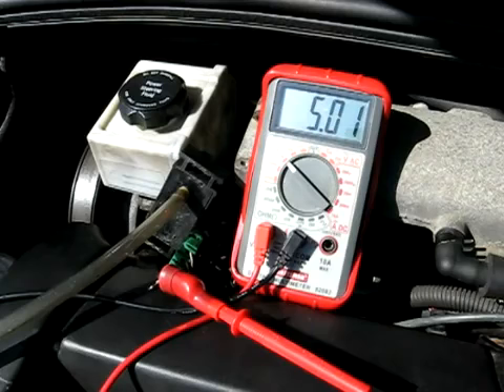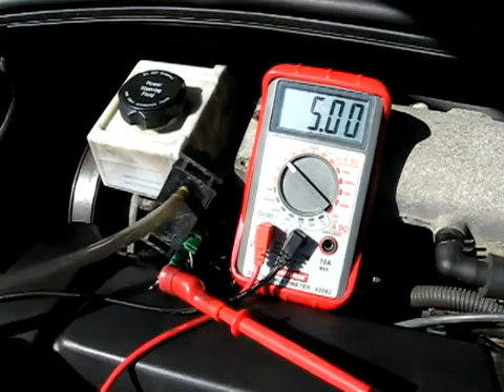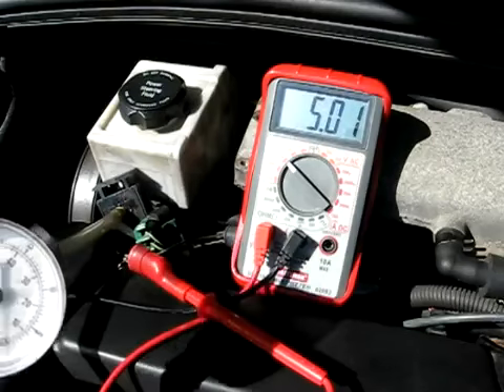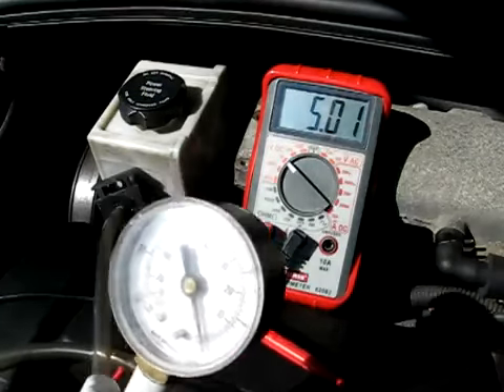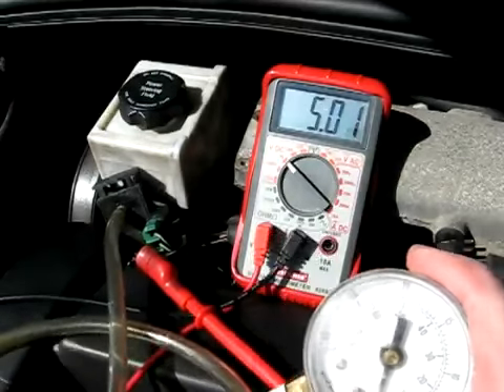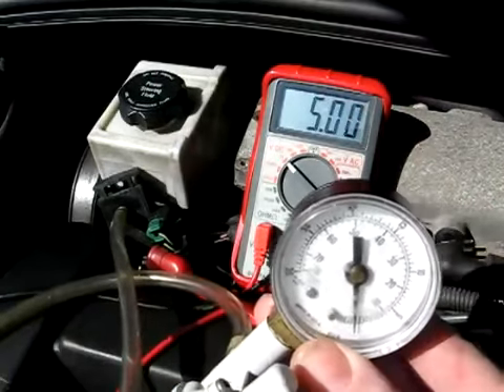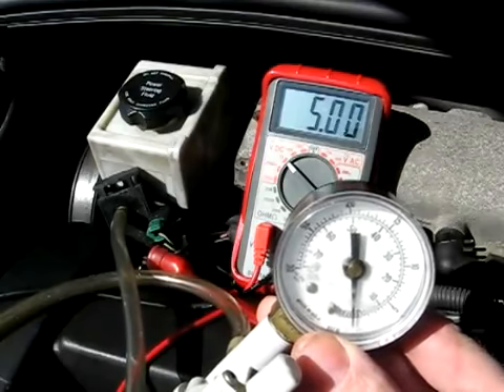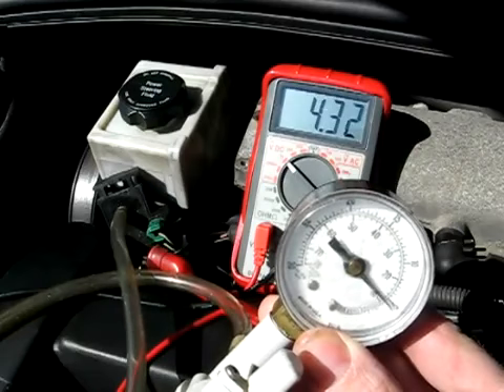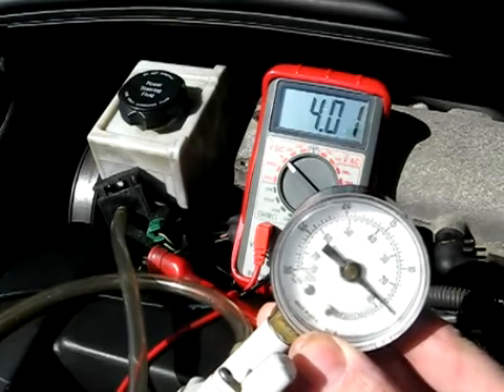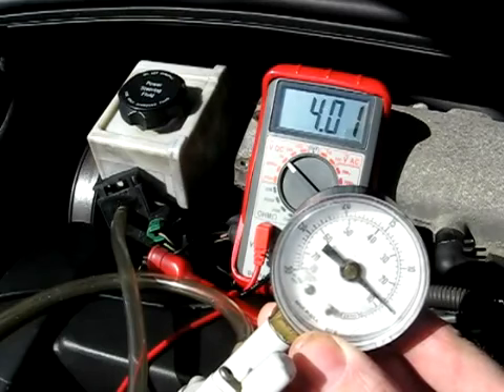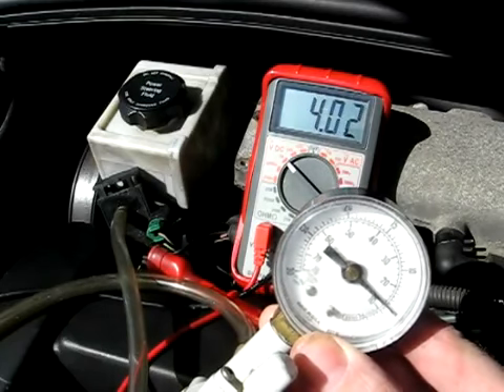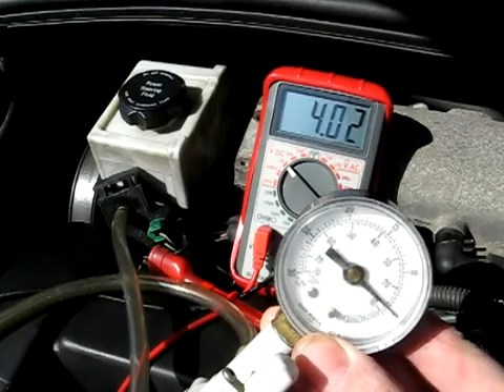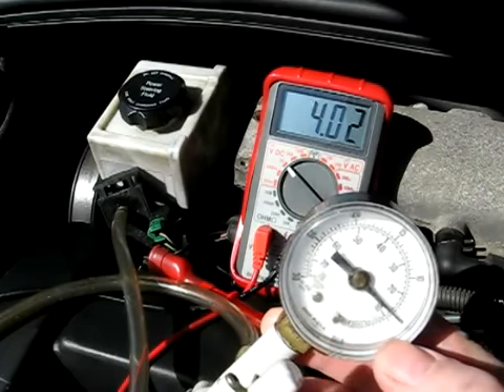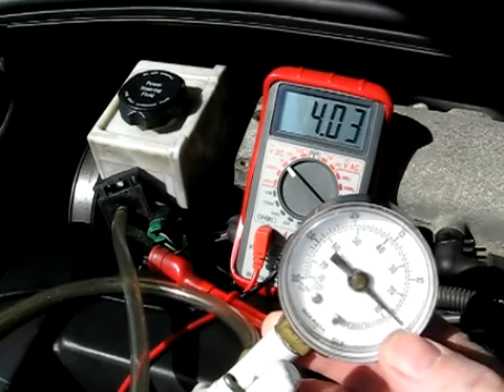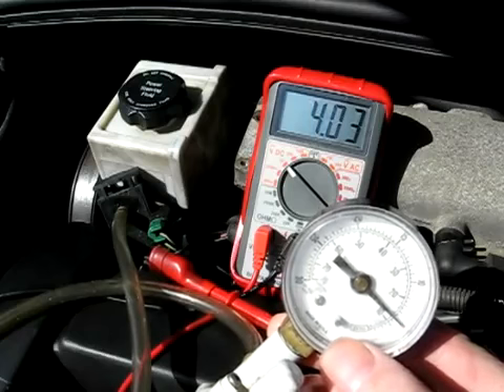That's correct. Now we're going to take our pump and pump the pressure. For every 5 pounds of pressure we should see something like a 1 volt drop on our meter. There's 5 inches of vacuum and we're getting 4 volts on our meter. That looks good.